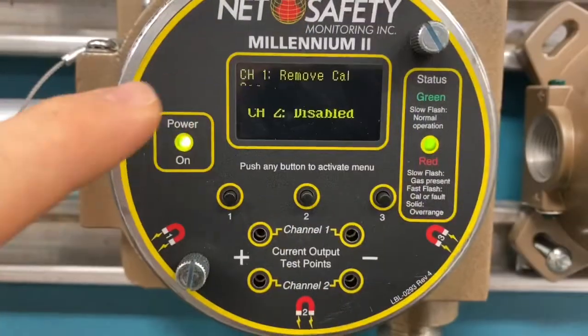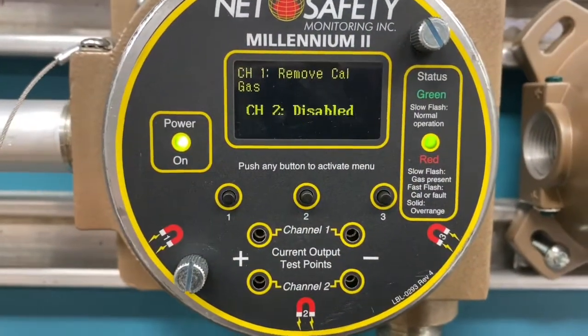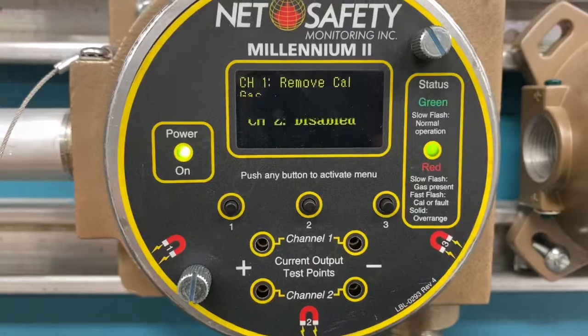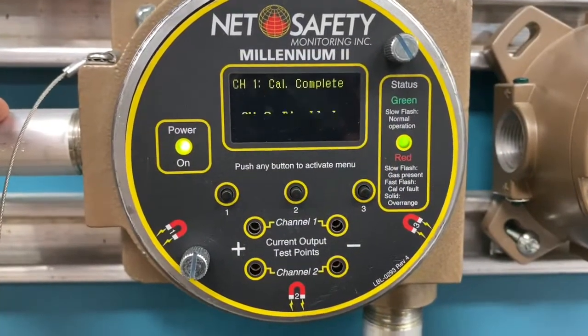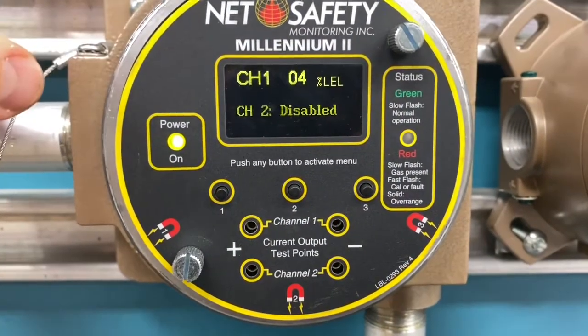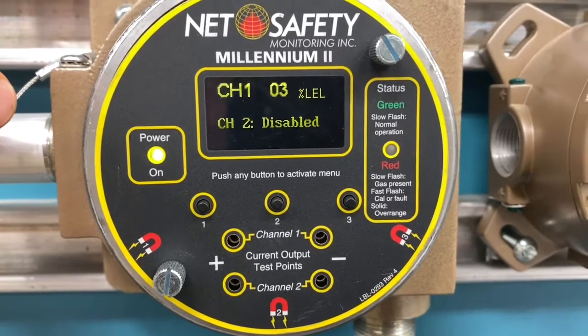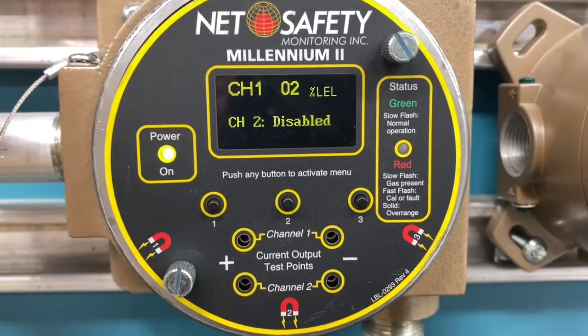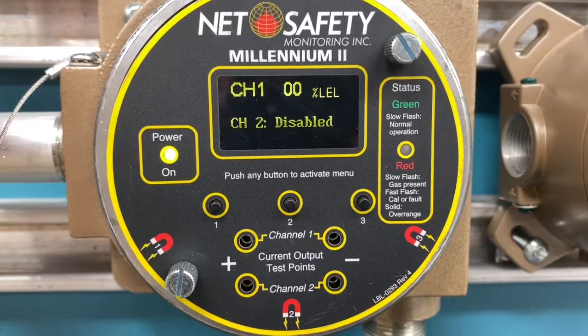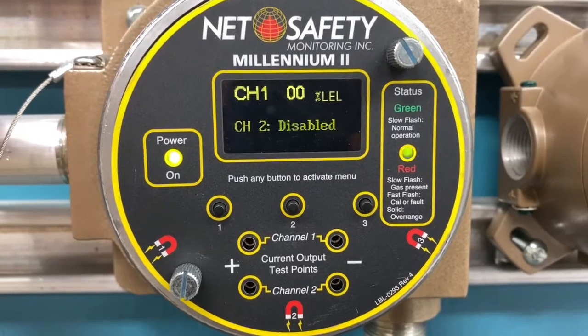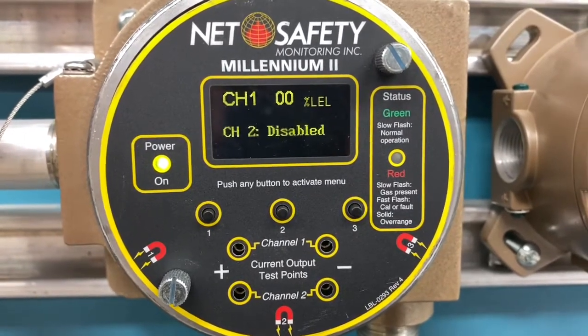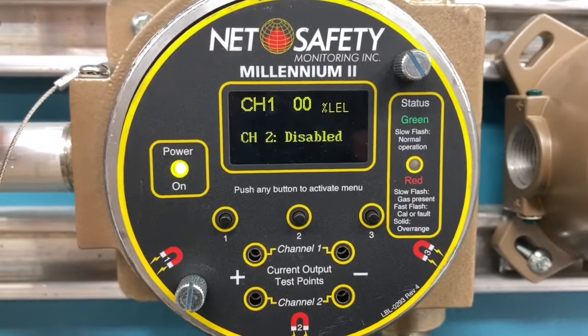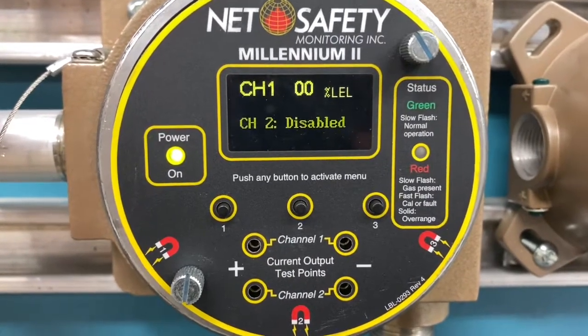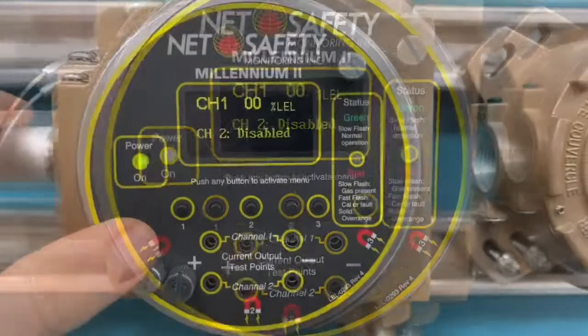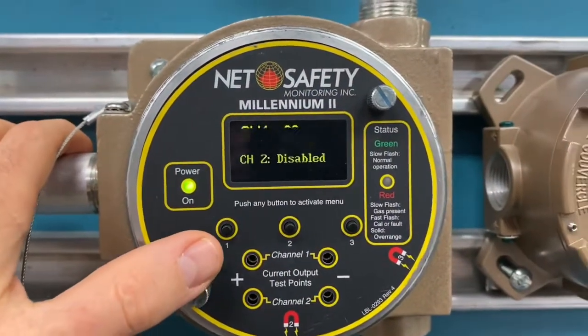So once everything's stabilized here, then it should confirm calibration. All right, there we got the remove cal gas prompt, so we can now shut off our cal gas. All right, so I removed the calibration gas, and I added the zero air, and you can see it's just coming down now to 0. It looks like the calibration worked. And yeah, it looks like it's going to hold steady at 0% LEL. So it looks like that fixed our problem. Just needed to be calibrated. The sensor had drifted.